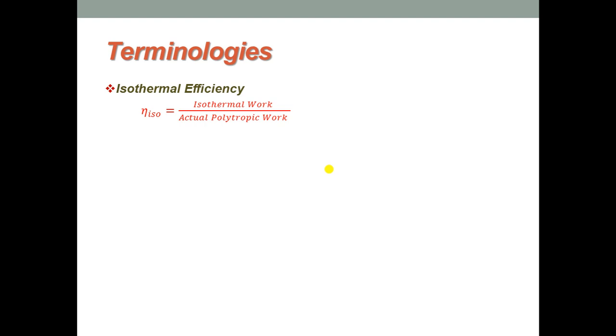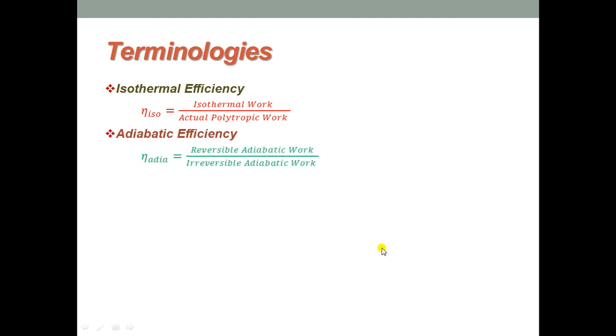Isothermal compression cannot be achieved in practice, but an attempt is made to approach the isothermal case by cooling the compressor, either by addition of cooling fins or water jackets. The second efficiency is adiabatic efficiency, defined as the ratio of work done in the compressor with reversible adiabatic compression to irreversible adiabatic work — mathematically, reversible adiabatic work over irreversible adiabatic work.